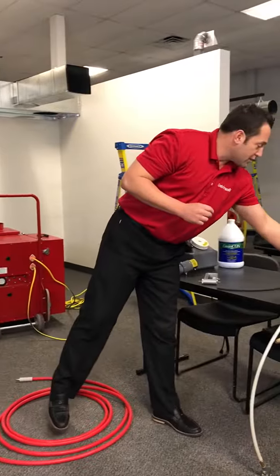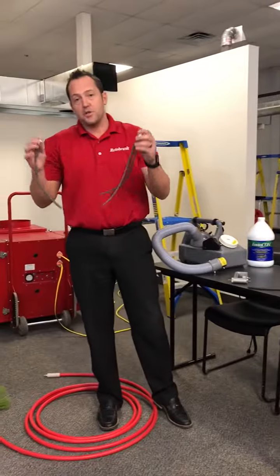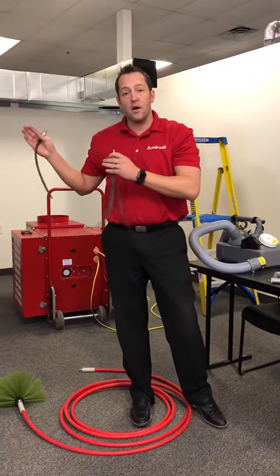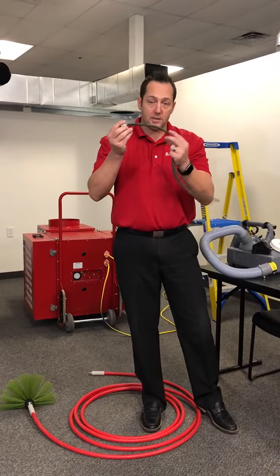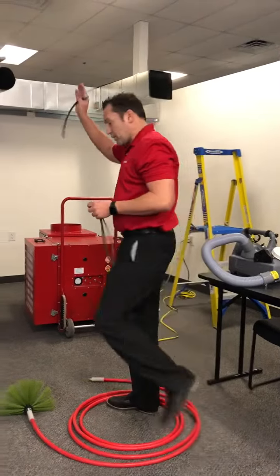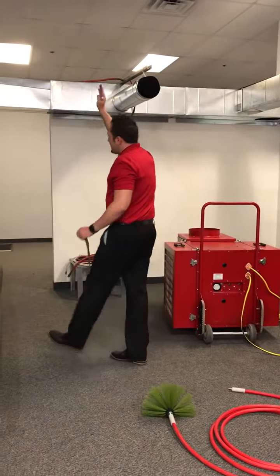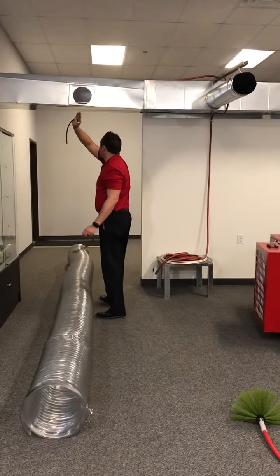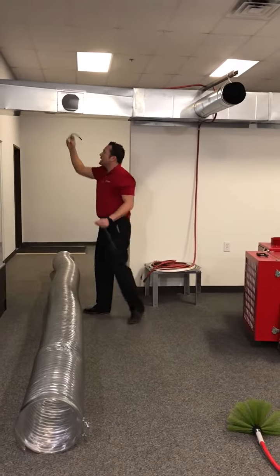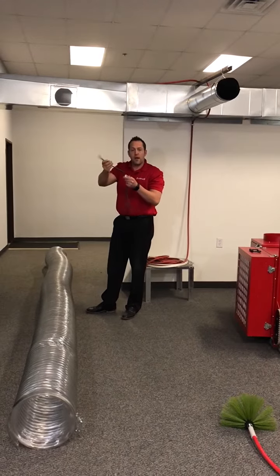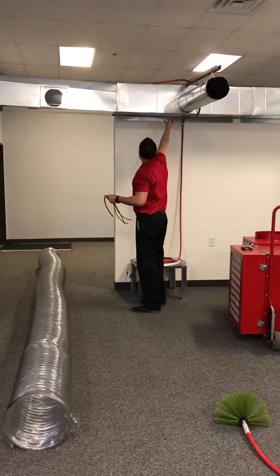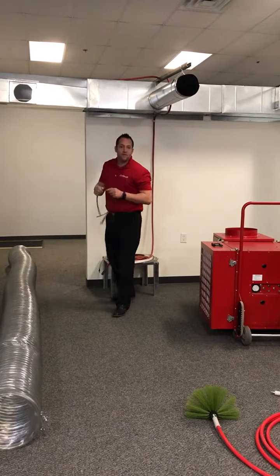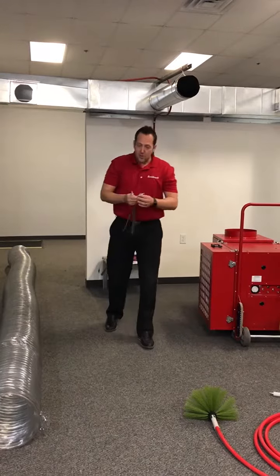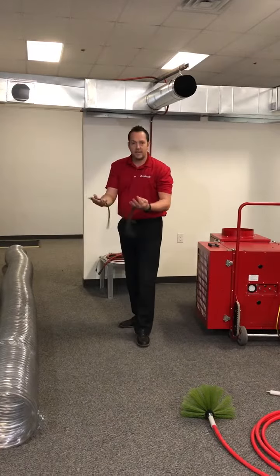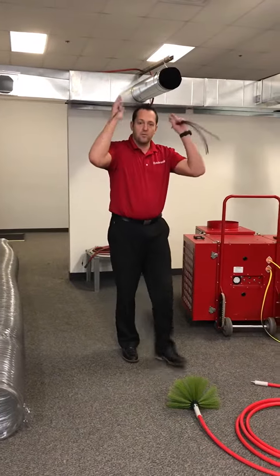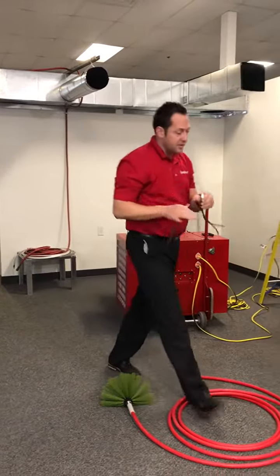The whip step, forward and reverse air sweeps we talked about before. Once you've brushed every duct inside the home, come back through with compressed air lines, again going from the furthest register from the air handler into each duct. There's a supply coming out here, you send it in, it blows from the tip, whips around, and blows that dust and debris back to the air handler in conjunction with the vacuum the R5000 is creating. As it bounces around, it takes the dust and debris you've dislodged, puts it airborne, and sucks it all the way back.